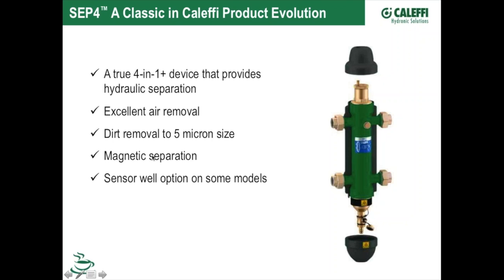The dirt separation itself does an excellent job. Now, we're saying down to a 5-micron size that we can filter out here as we go through that media. Now, bear in mind, it'll take multiple passes to get those smallest particles out. It doesn't get everything the very first time like you might expect with a cartridge type of filter where everything goes through it, everything is trapped by the size of the filter. This does take a few passages through there. I think on our website we show the performance, and in the data sheet that comes with it, we show the performance typically at 20 and 50 passages through there, that we're going to get down to that very small micron particle pulled out of the fluid stream.